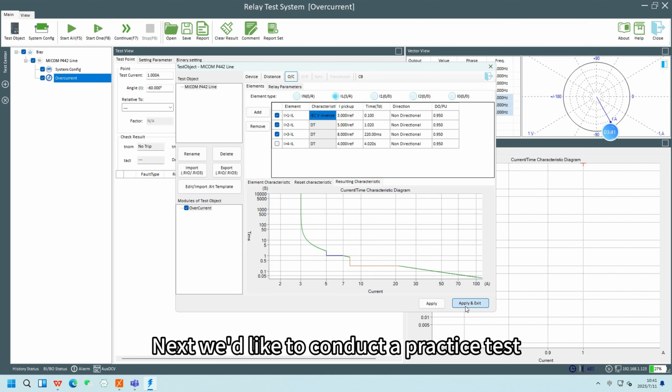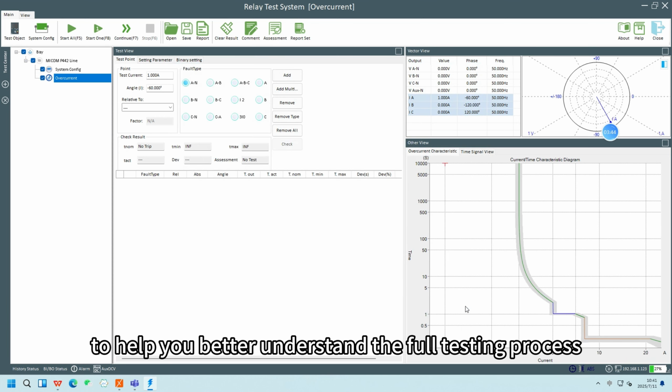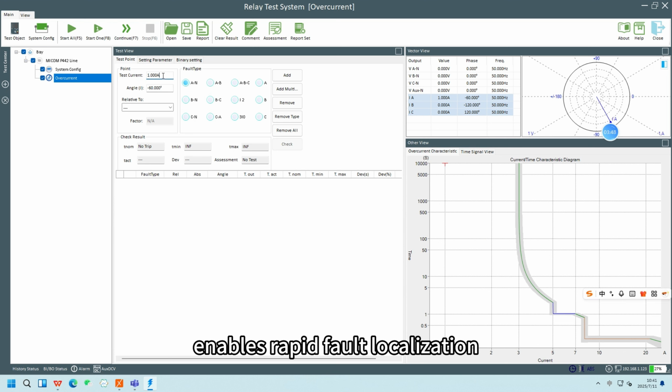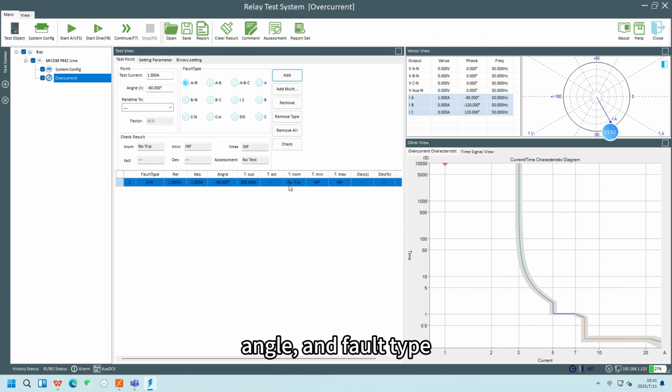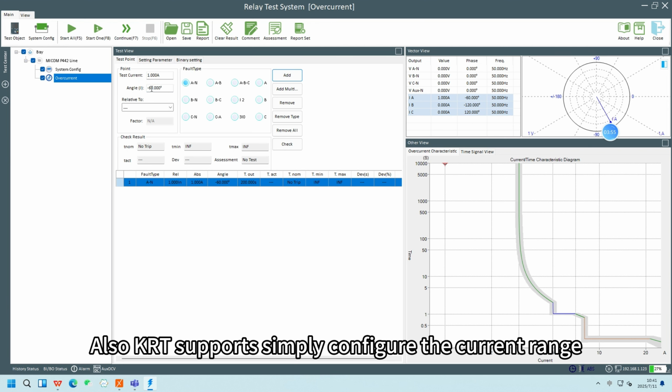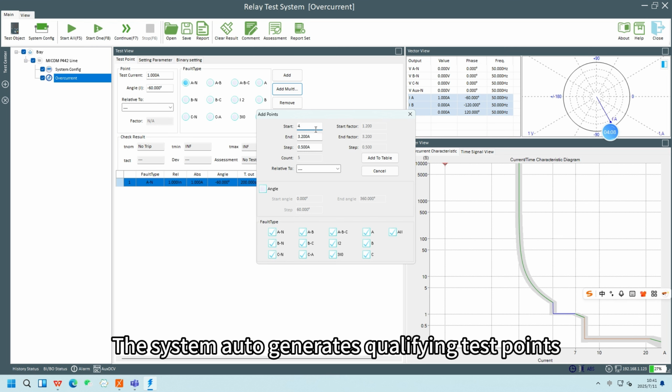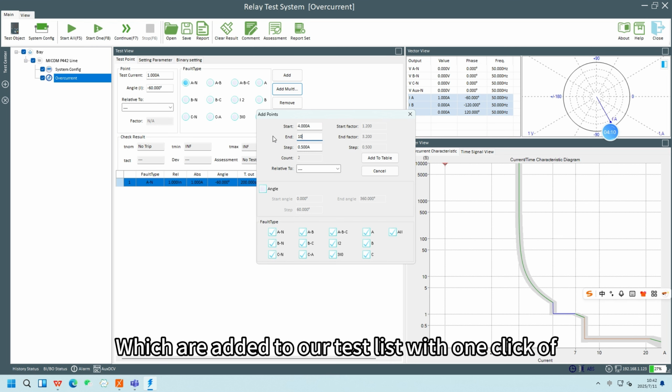Next, we'd like to conduct a practice test to help you better understand the full testing process. The test point interface enables rapid fault localization to add test points by checking current, angle, and fault type. Also, KRT supports simply configuring the current range, for instance start, end, step, and selecting fault type and angle. The system auto-generates qualifying test points, which are added to our test list with one click of Add to Table.